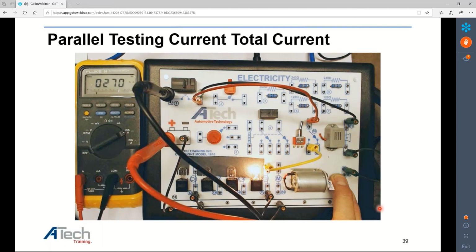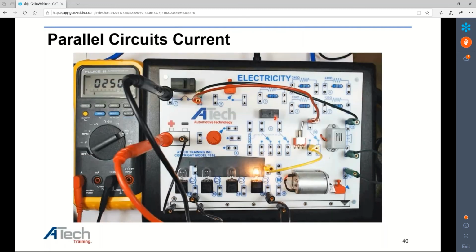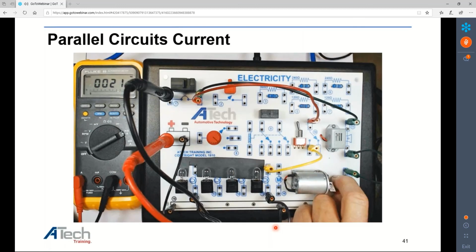If I go over here and do this again, I have 250. Notice I don't have this other circuit activated over here, so my amperage dropped to 250 milliamps. That bulb's pulling 250 milliamps through that circuit. Now if I push this lead and turn off my light circuit, I'm reading 21 milliamps. That's how we get our circuits.